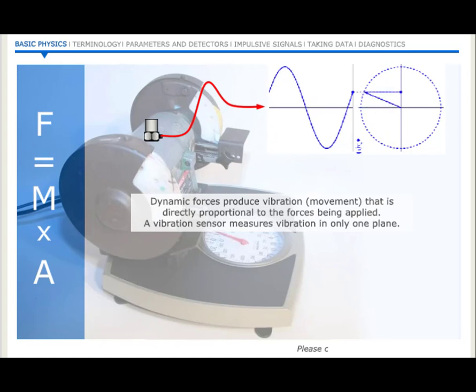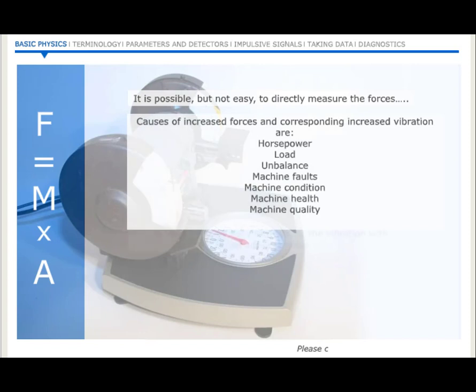So if we look on our instrument at what happens as the vector rotates, we see a sinusoidal waveform representing the effect of the forces acting upon the machine. It is the forces acting upon a machine that are the cause of vibration. Vibration is not a cause of a problem, it is a symptom. If there are any mechanical tolerances in the build of a machine that allow movement, then the resulting movement will correspond to the amount and direction of the force that is being applied.